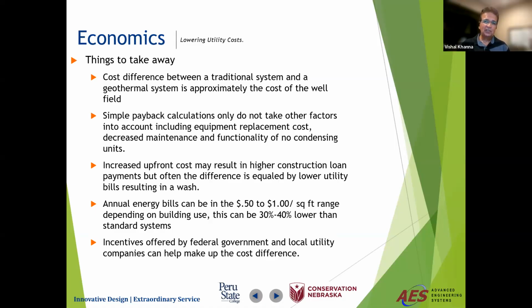The biggest issues you see with geothermal systems - we've gone in and corrected a lot of other projects designed by others - the biggest issue is the sizing of the boreholes in the well field. Has it been done correctly? Do you have enough heat exchanger capacity?